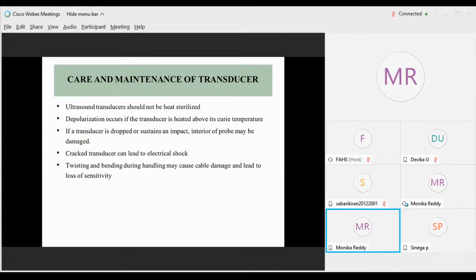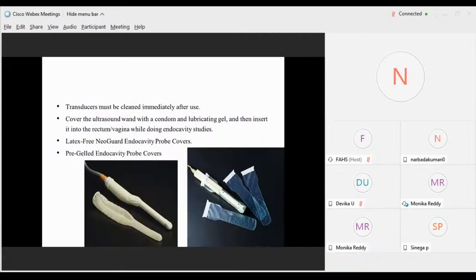If a transducer is dropped, we have to check whether the interior of the probe may be damaged. So we have to check regularly. If any crack happens, it will lead to electrical shocks for the patient. Twisting and bending during handling may cause cable damage, which leads to loss of sensitivity of the pulses. The transducers must be cleaned immediately after use, and they should be covered whenever endocavity studies are happening.